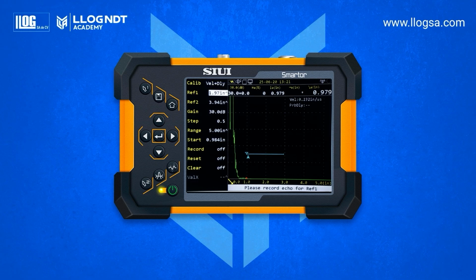You'll need 2 known references. In reference 1, enter the lower value. In reference 2, enter the higher value from the reference block. It is important to note that the values of these and other settings may vary depending on the test conditions and the type of material being inspected. Therefore, equipment configuration may differ from one application to another.